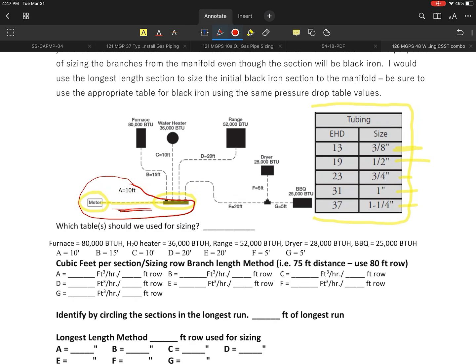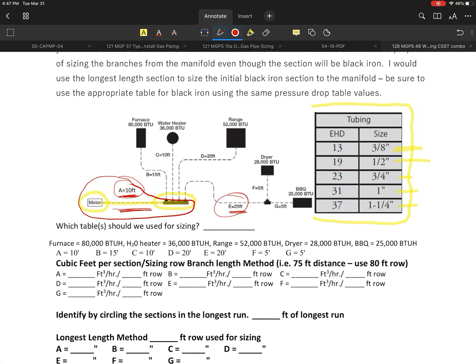You want to use the longest length section to size that initial part using the black iron table. But then once you figure that size out, disregard that table and go to the corrugated stainless steel table. But don't forget to include that extra 10 feet. So that 10 feet is going to have to get added to, let's just say for example if this is my longest run. If that's the case, I would have to be adding the 10 plus another 20 plus whichever the next two are longer.